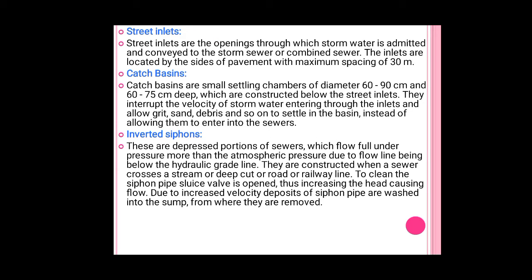First is the street inlets. Street inlets are the openings through which the stormwater is admitted and conveyed to the storm sewer or combined sewer. The inlets are located by the side of the pavement with a maximum spacing of 30 meters.